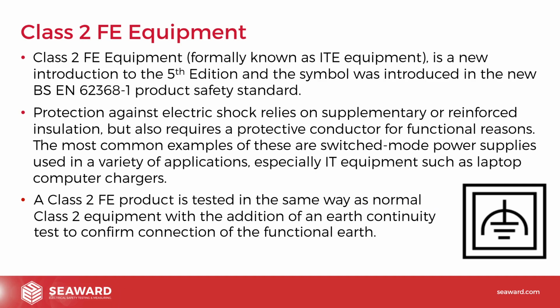Now, another change in terminology, or another introduction to the code of practice that we need to be aware of, is Class 2 FE, Class 2 Functional Earth, that stands for. So Class 2 FE equipment, formerly known as ITE equipment, is a new introduction to the 5th edition. And the symbol was introduced in the new BS EN 62368 product safety standard. You can see in the bottom right hand corner there's a new symbol that was introduced in that EN standard to cover Class 2 FE equipment.